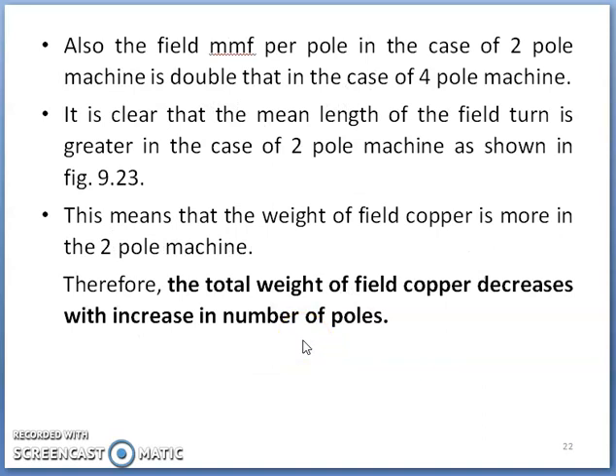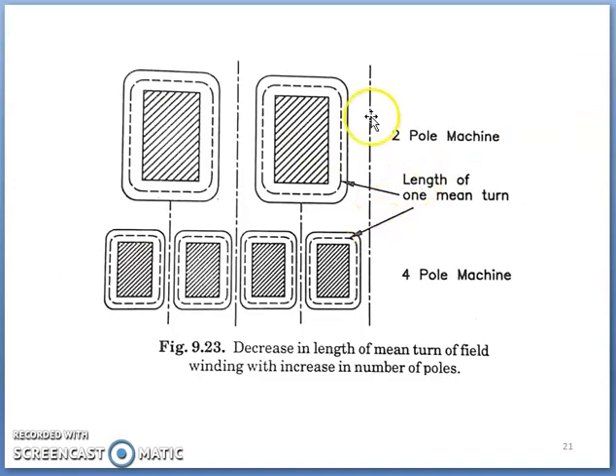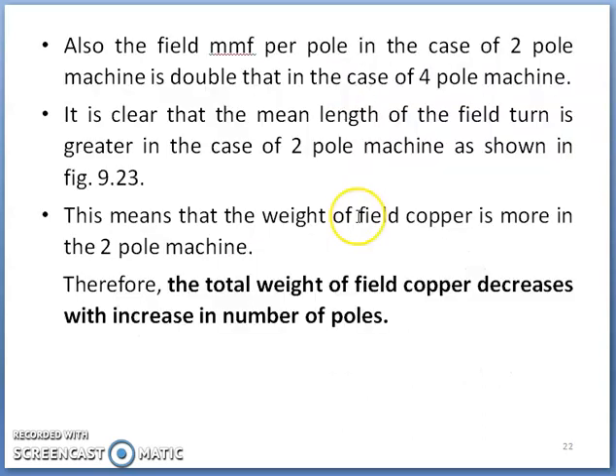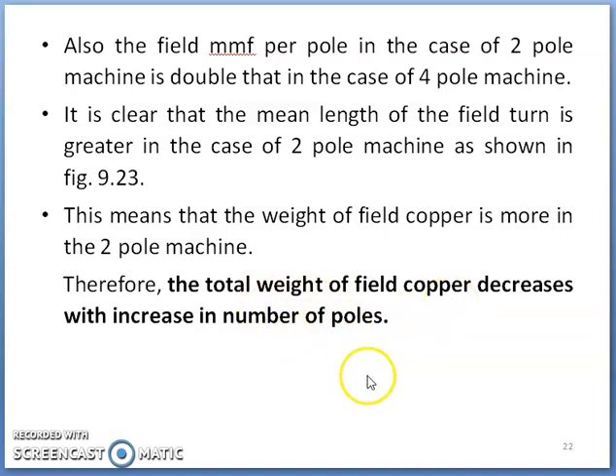As the field MMF per pole in the case of a two-pole machine is double that of a four-pole machine, the mean length of turn is greater in the case of a two-pole machine, as shown in the figure — the field section is larger. Because of this, the weight of field copper is more in the case of a two-pole machine. Therefore, the total weight of field copper decreases with increase in number of poles. If number of poles are increased, depending upon field MMF per pole, the requirement of field copper changes and hence total weight of field copper decreases.